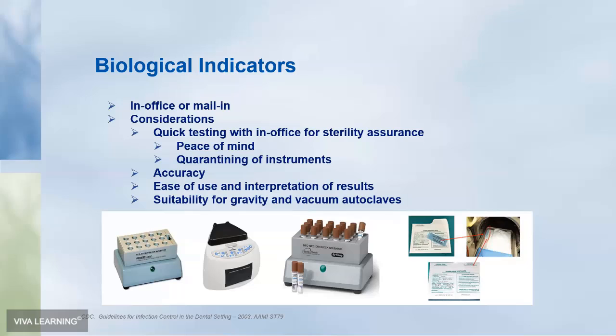In-office biological indicators or monitoring does help comply with best practice guidelines established by the CDC. It states that steam sterilizers should be monitored at least weekly, preferably daily. They're quick, accurate approaches to steam sterilizer biological monitoring, and they've been tested. We can see several here. All of these are user-friendly. They're suitable for gravity and vacuum autoclaves, so you don't need different spore tests for different autoclaves if you have more than one type in the office.